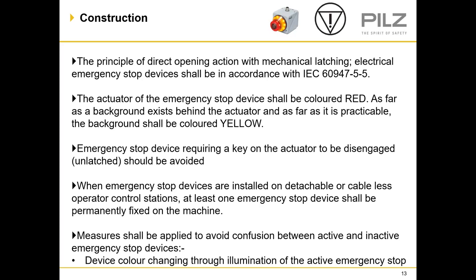When emergency stop devices are installed on detachable or cableless operator control stations, at least one emergency stop device shall be permanently fixed to the machine. There is a discussion regarding using RFID sensors for emergency stop functions, although this is pretty unlikely as most RFID sensors are non-contact actuating devices and there isn't a physical rigid member that directly affects the contacts. The colouring of them may also not satisfy the standard of being red on a yellow background.